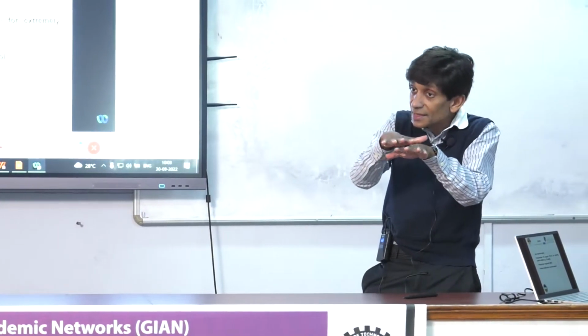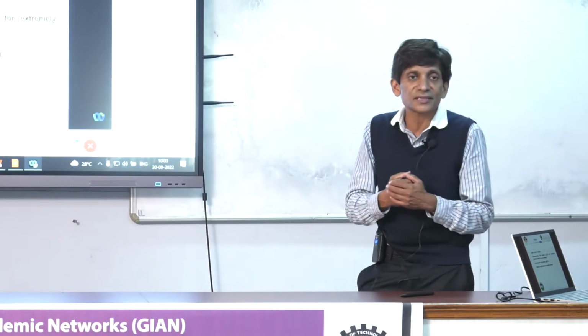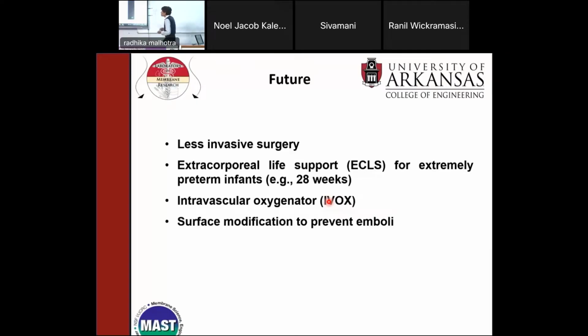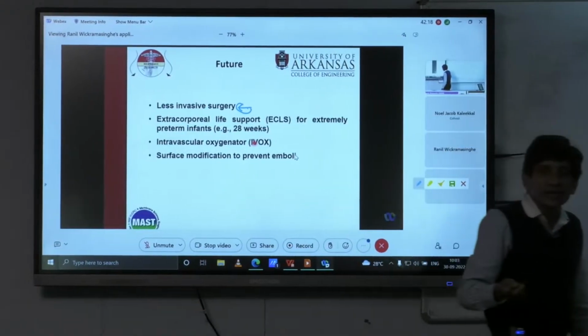And then the most recent development were these microporous blood oxygenators, which I talked about. And here we have a microporous membrane. There is still a gas-liquid interface, but it's relatively small because it's all these micropores. So you minimize blood damage. You have high rates of gas transfer, okay? And these were used routinely in the late 80s, 90s, 2000s. But the future is moving towards less invasive surgery, okay? Today there are many procedures that in the past were very difficult because we had to operate, but today if we can avoid operations, it's good because the patient recovers much more quickly.